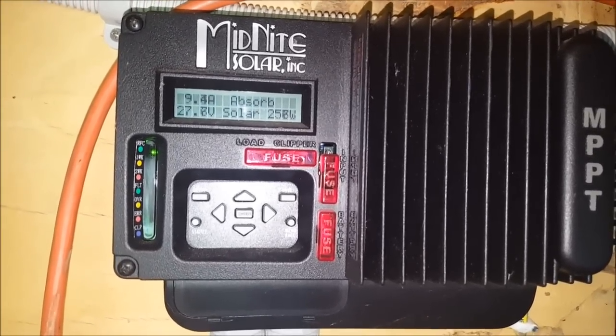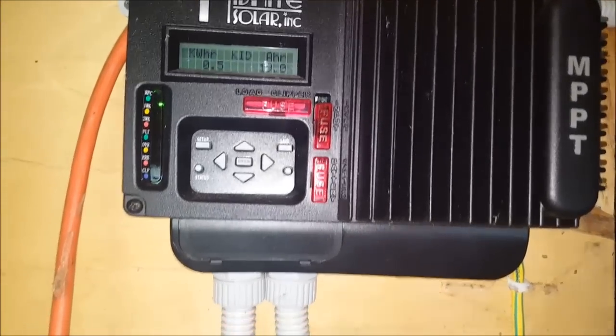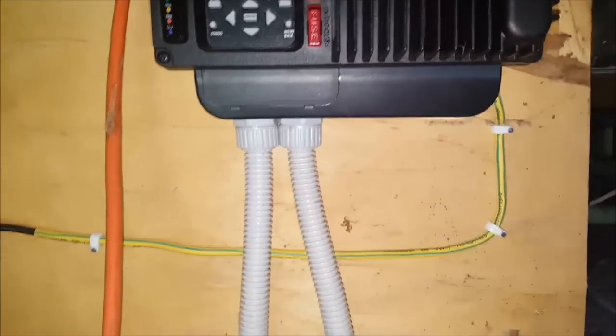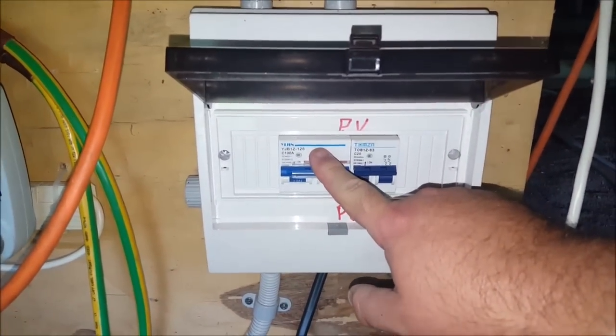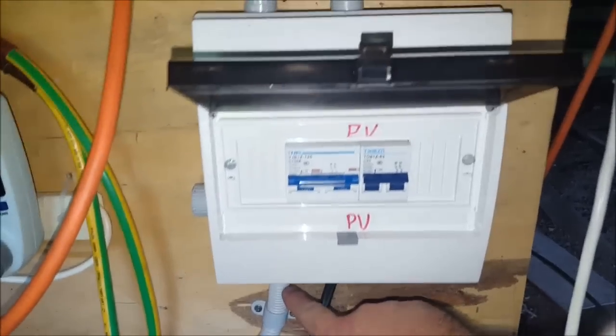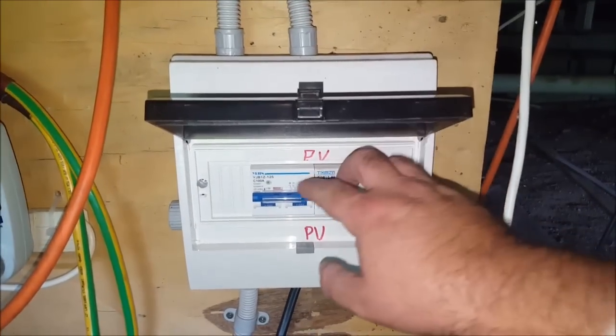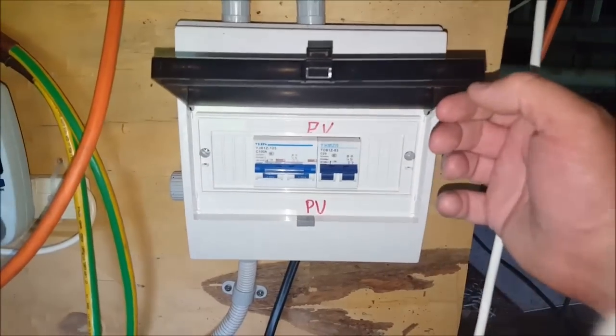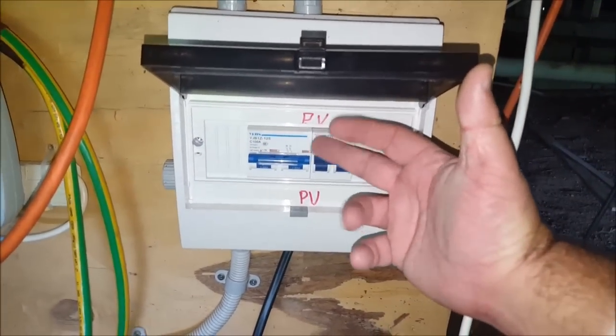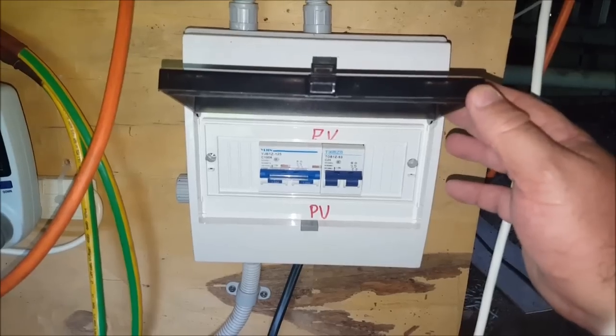You've just seen how overcast it is today, and the charge controller is in absorb mode. The cable comes back down to this circuit breaker and out to the back of the inverter — I'll show you that shortly. I've got these circuit breakers here mainly so that I can electrically isolate the charge controller if I need to change any configurations. So it's just a matter of flipping both of these off and the charge controller is then isolated.